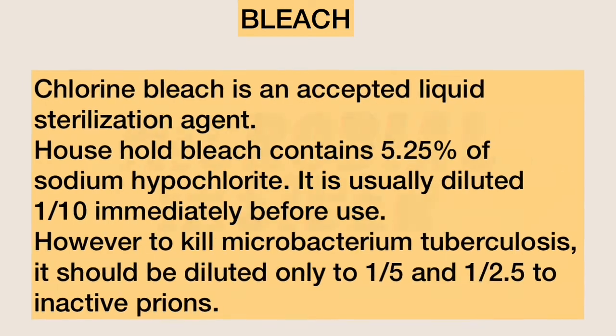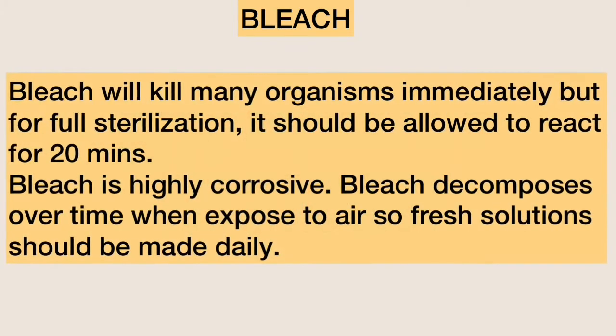Secondly, we have bleach. Chlorine bleach is an acceptable liquid sterilization agent. Household bleach contains 5.25% sodium hypochlorite and is usually diluted to one-tenth immediately before use. However, to kill Mycobacterium tuberculosis, it should be diluted to one-fifth, and to one-two-and-a-half to inactivate prions. Bleach will kill many organisms immediately, but for full sterilization it should be allowed to react for 20 minutes. Bleach is highly corrosive and decomposes over time when exposed to air, so fresh solutions should be made daily.